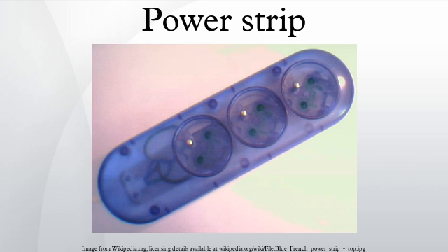Within the EU, power strips with surge suppression circuits can demonstrate compliance with the Low Voltage Directive 2006/95/EC by complying with the requirements of EN 61643-11:2002 plus A1. The standard covers both the performance of the surge suppression circuit and their safety. Likewise, power strips with telecom surge suppression circuits can demonstrate compliance with the LVD by complying with the requirements of EN 61643-21:2001.